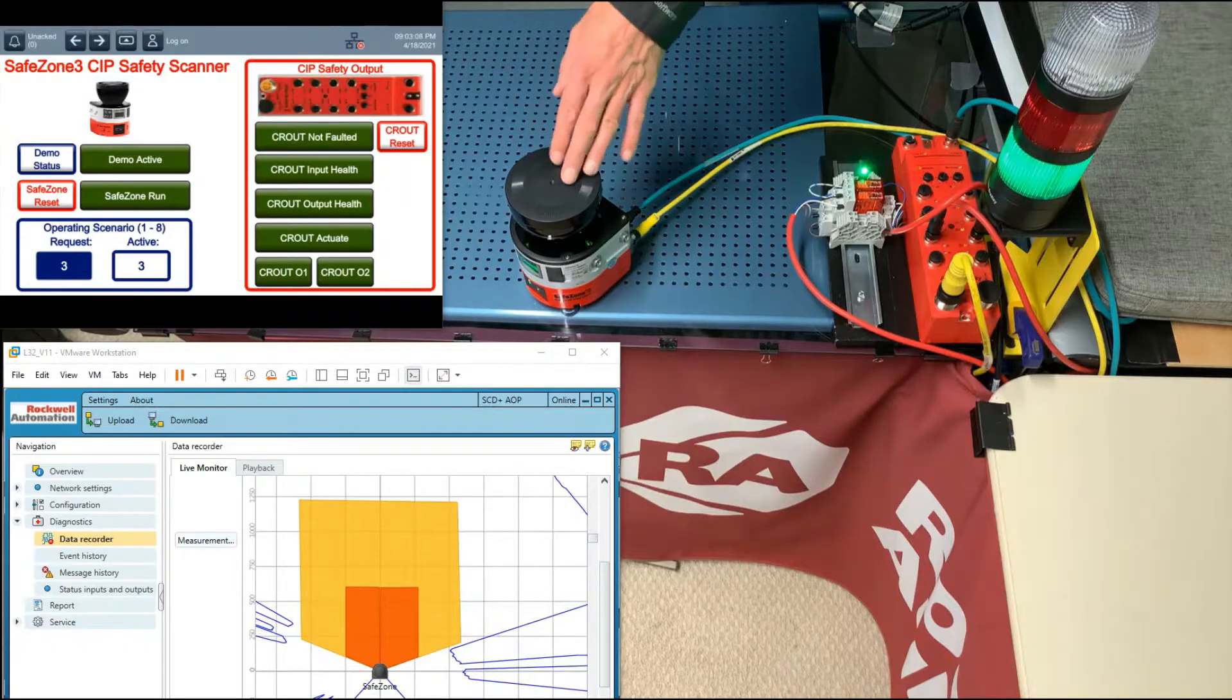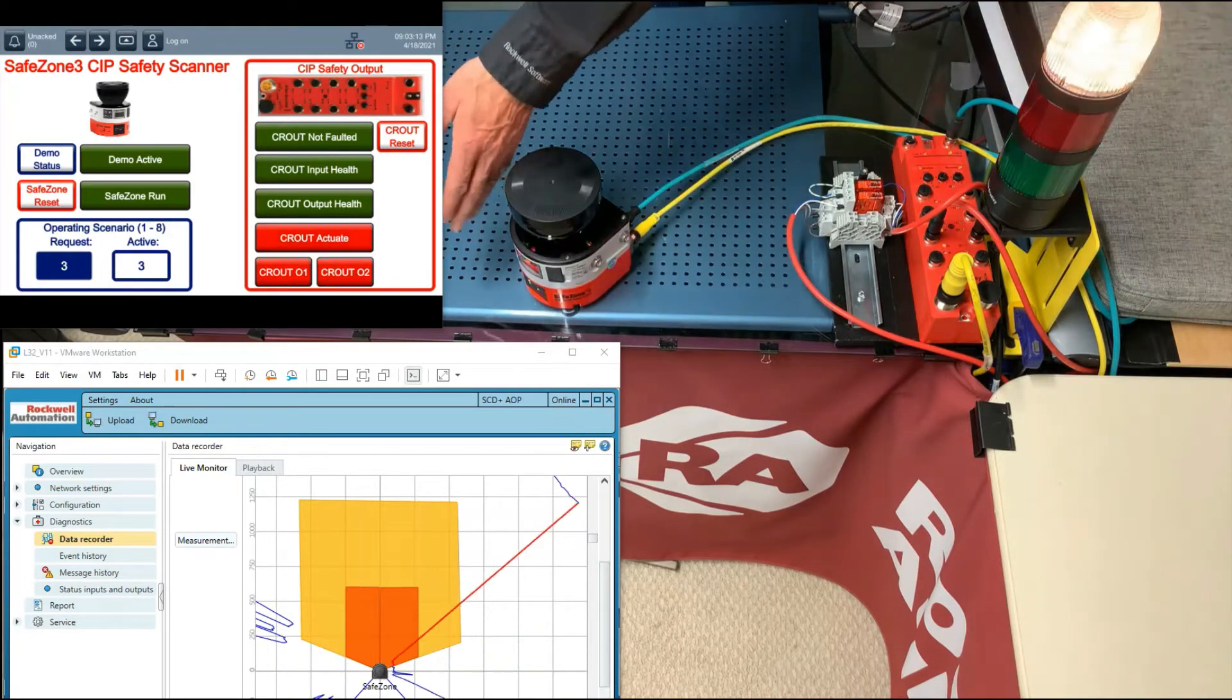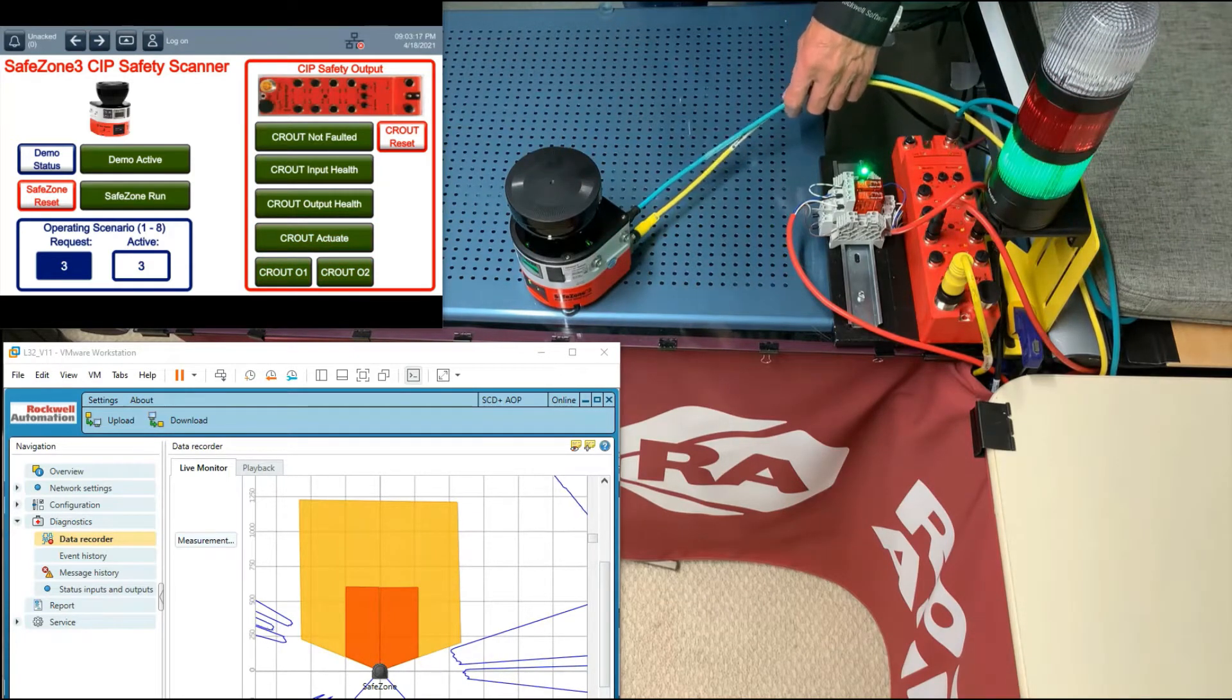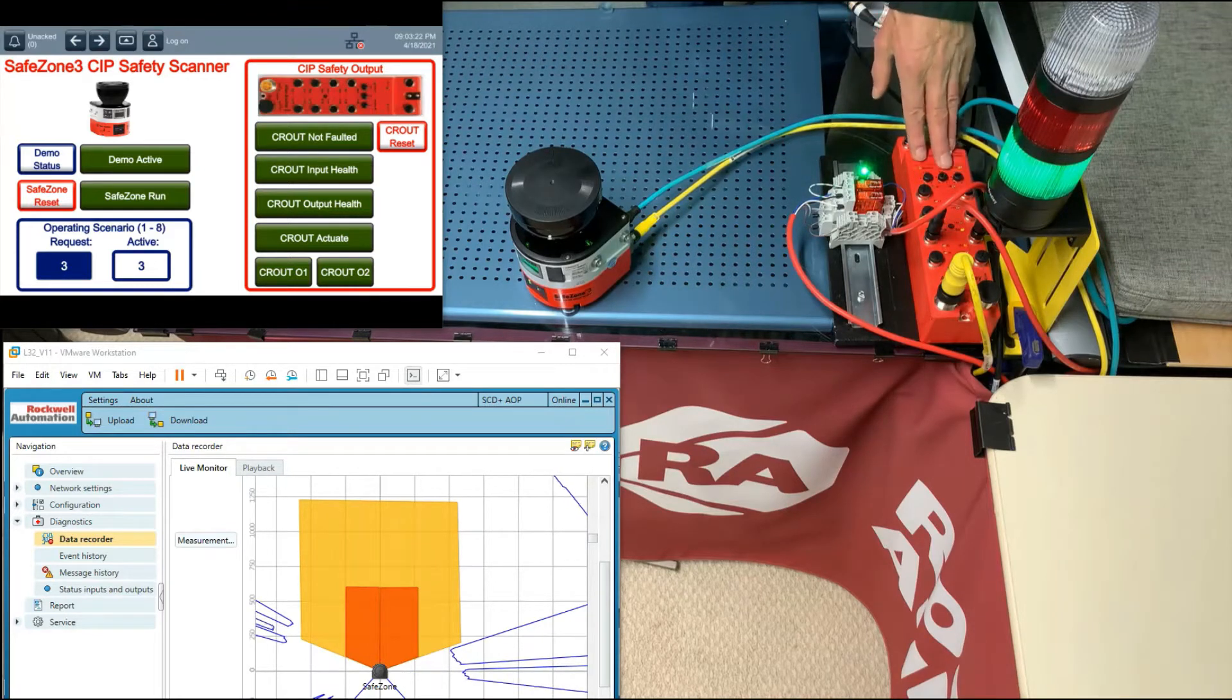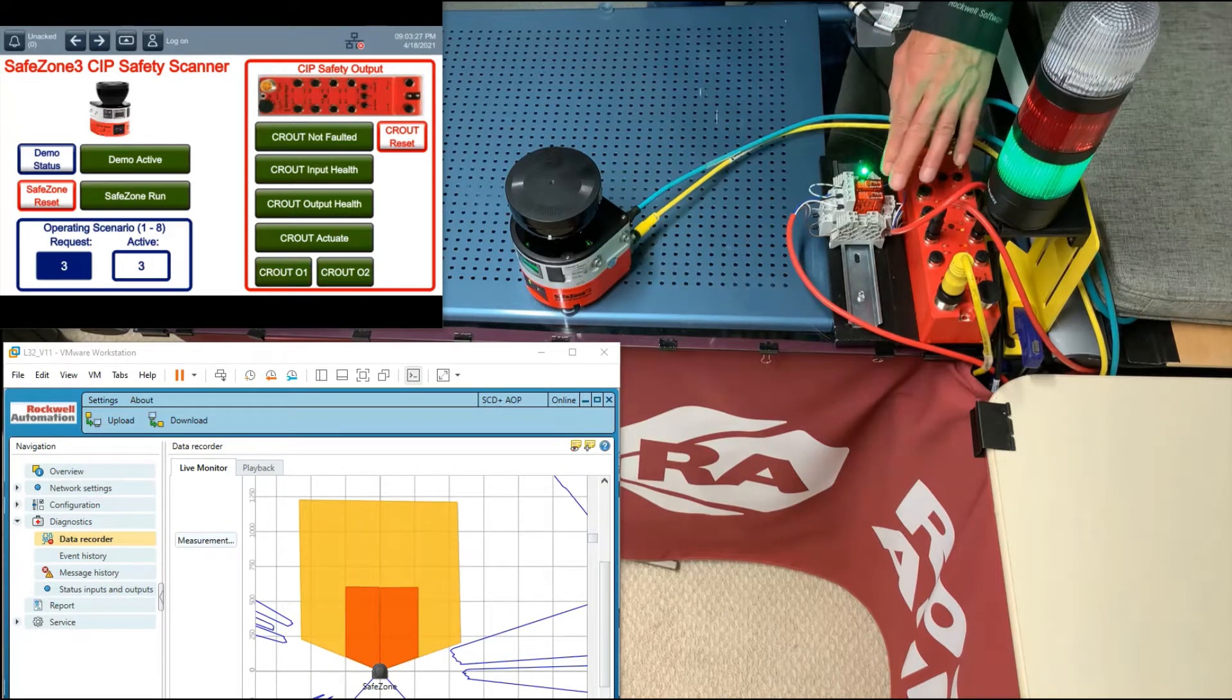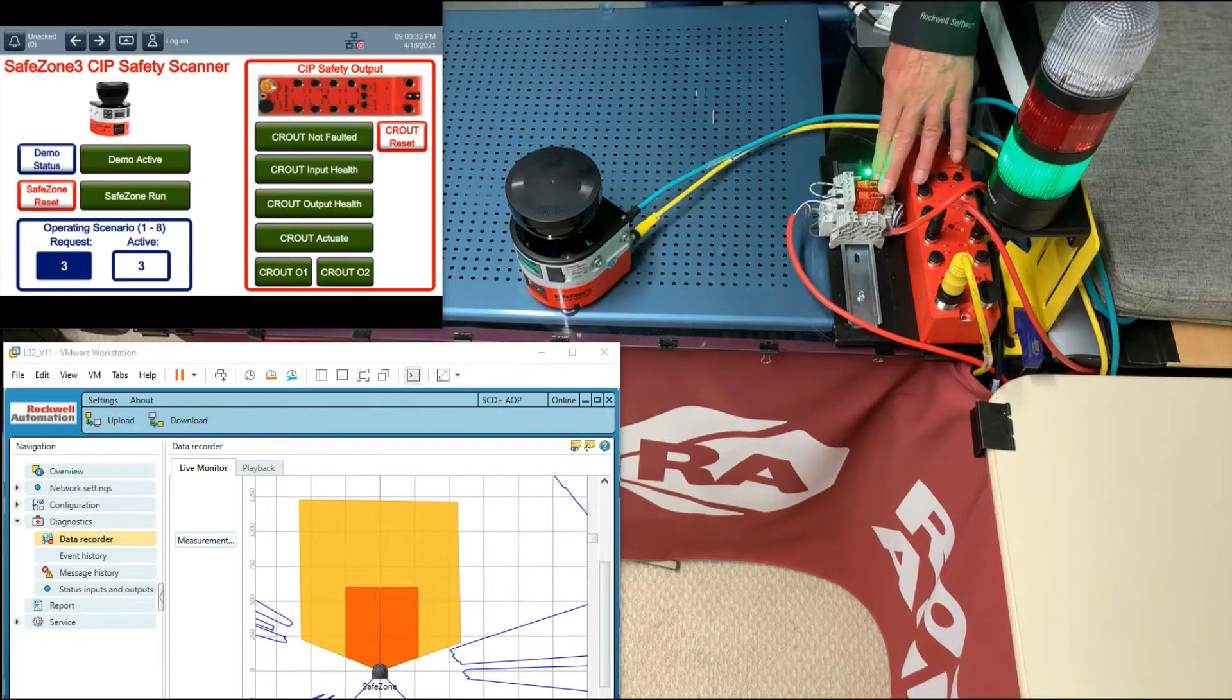We're simulating a production scenario where the SafeZone 3 is protecting two sides of a palletizing cell. The SafeZone is connected via CIP safety to GuardLogix, which includes this panel view. GuardLogix uses a configurable redundant output latch instruction with this armor block guard I/O to two safety control relays and corresponding inputs for discrepancy testing.